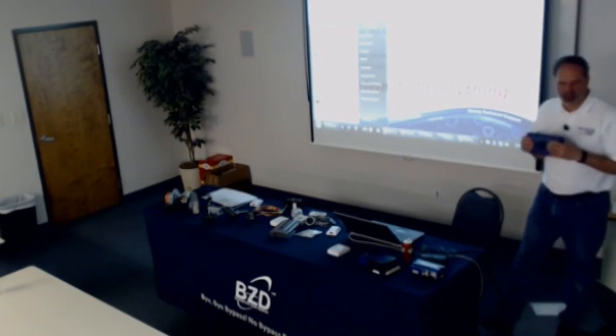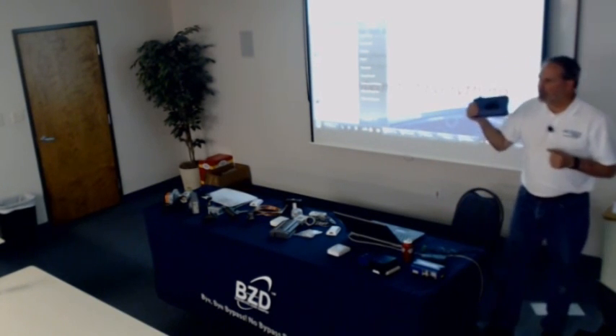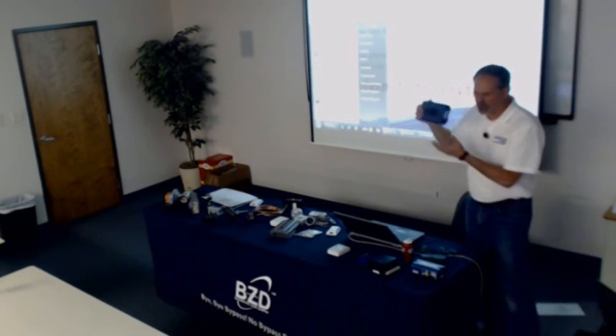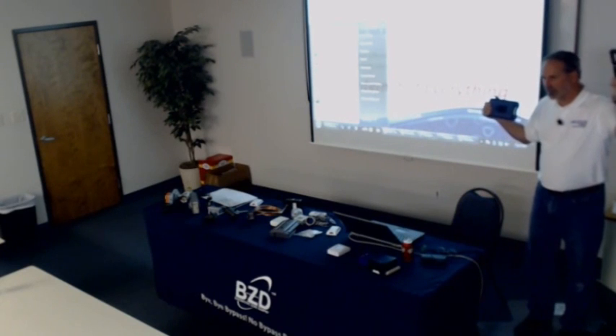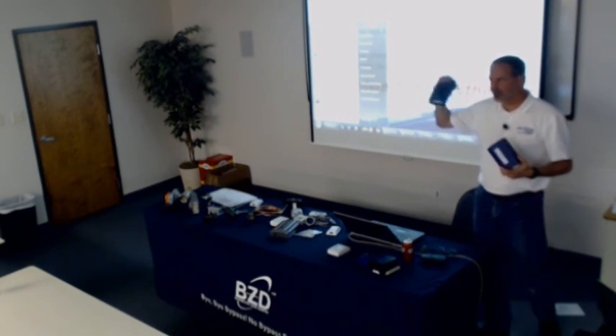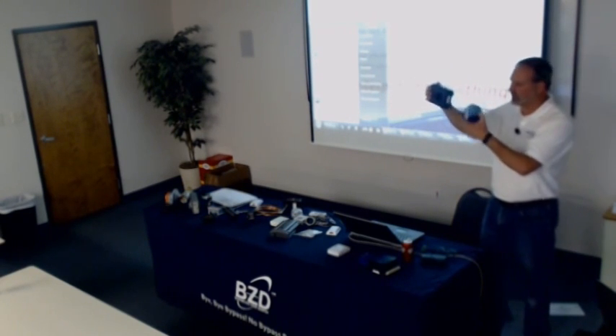Okay, so the question was, if you have this controller with a small screen on it, can you look at it remotely? The answer is not really. I'm not 100% sure what they meant by remotely. I guess if you run a wire to it and run it to your laptop, you could see it remotely. But if you really want to see what's inside this controller remotely, it really has to either talk LON or BACnet down to a Tridium panel, and the Tridium panel is where the graphic for this guy is held today. Not in the future. In the future, the graphic will be held right here. So you will be able to look at it remotely over its IP address. But today, for the most part, this device here is not BACnet over IP, so it talks BACnet to the Tridium panel, and the Tridium panel holds the graphic and puts it out over the Internet so that we can all see it. So in general, you cannot see this screen remotely.